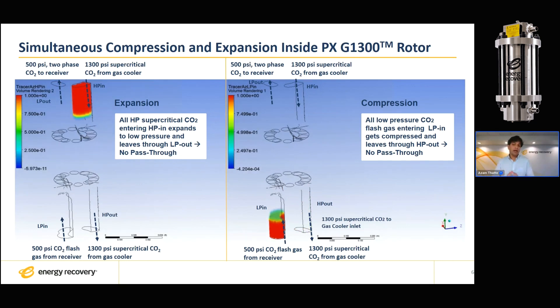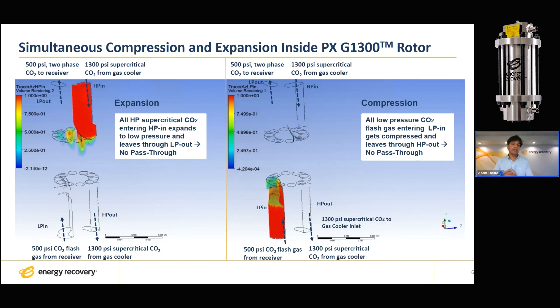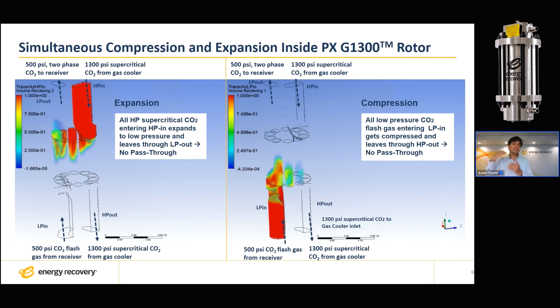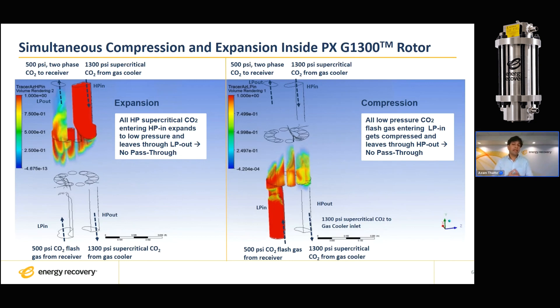And then the duct eventually gets exposed to the high-pressure port. As soon as the duct is exposed to the high-pressure port, there is a compression wave or acoustic wave that sets in, propagates back and forth inside the duct, and compresses that low-pressure flash gas into a high-pressure supercritical CO2 to the same pressure as the gas cooler pressure. Now, where is it extracting this energy required for this compression? There is no external mechanical or electrical energy required for this compression.